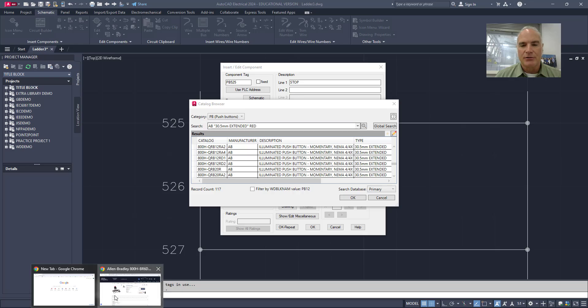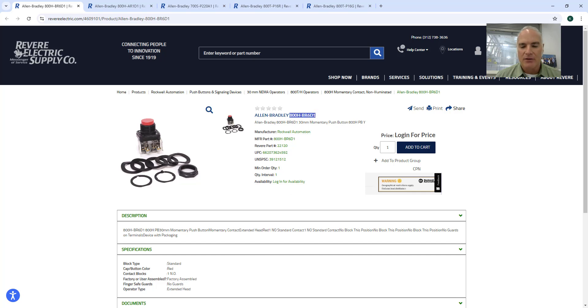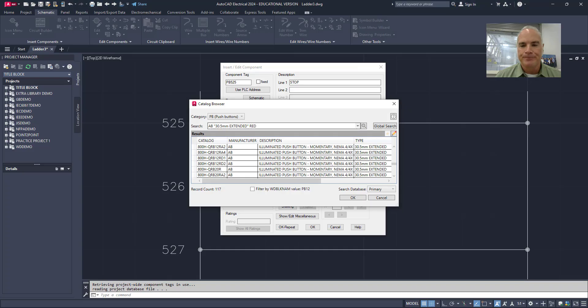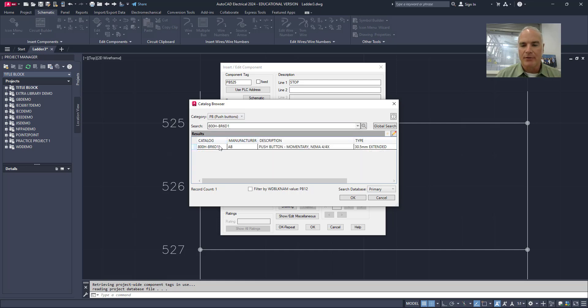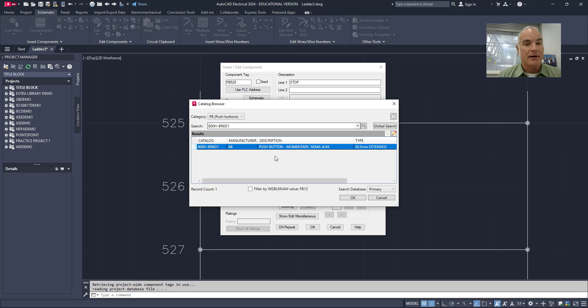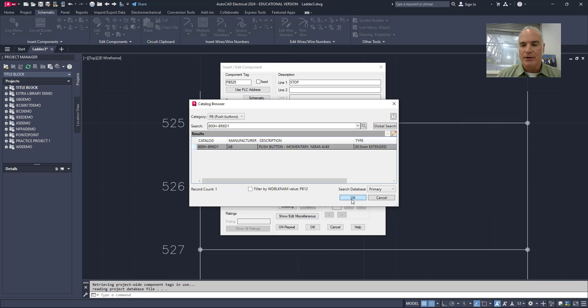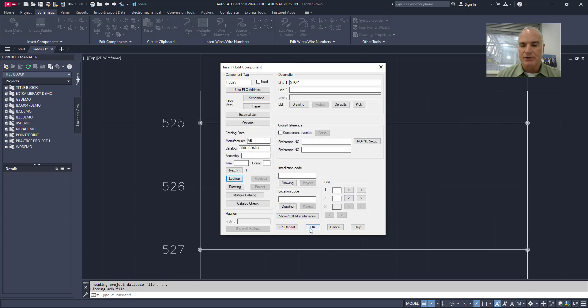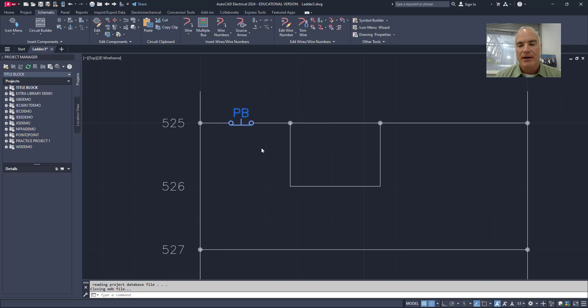And I could go through this list and I could find the one that I want. But in this case, I actually have one that I want. So I'm going to go to this diagram right here. And the one that I want is this Allen Bradley 800H BR6D1. So I'm just going to copy that information, go back to AutoCAD and paste that into my search bar right here, press enter. And you'll see that it brings it up. So now it's going to keep all of this information in the drawing. And if later on, I want to create a bill of materials or a purchase order, I can simply query how many of these are in there. I'll choose OK and then OK, and it asks me to map this to a catalog number. Yes, I do. And then it finishes it, puts it in there. It's a stop button, push button 525. The number 525 is because it's on line 525.